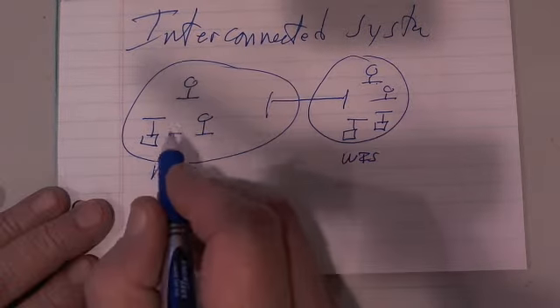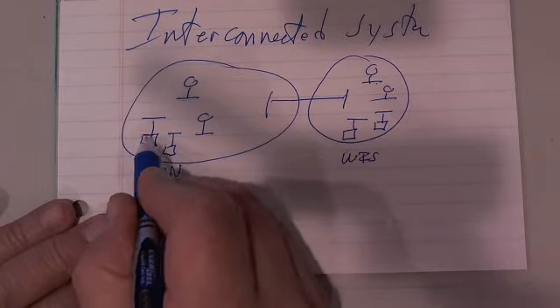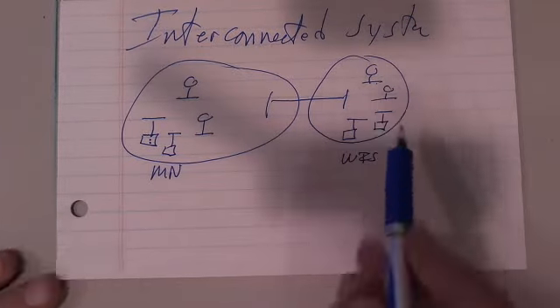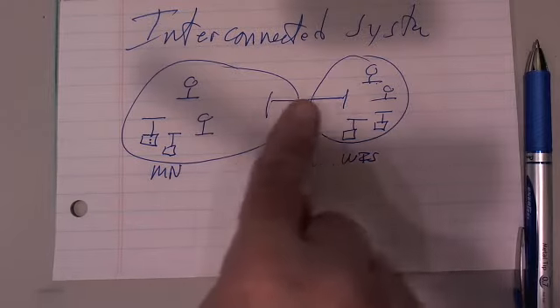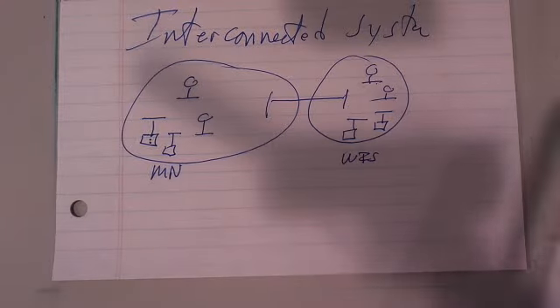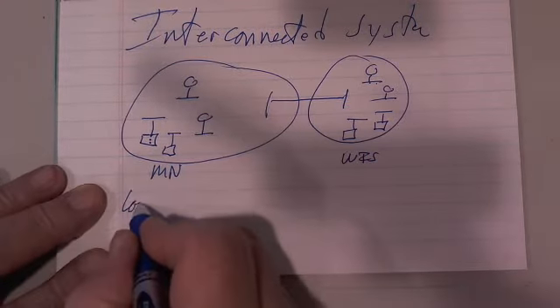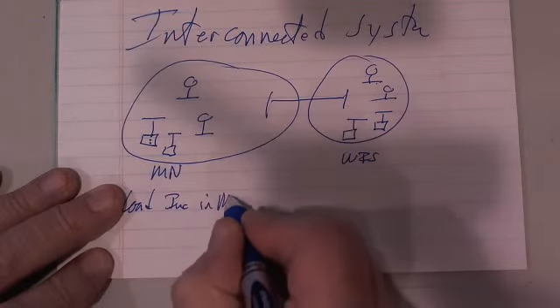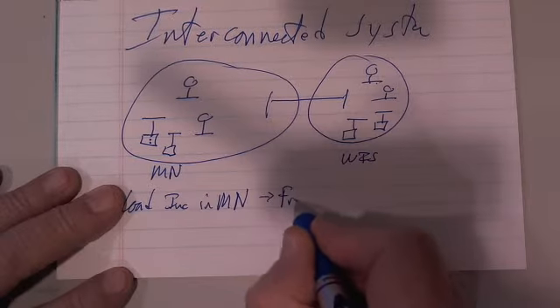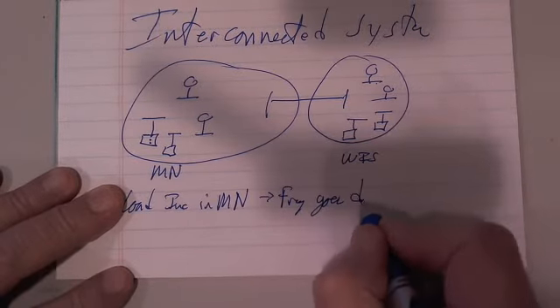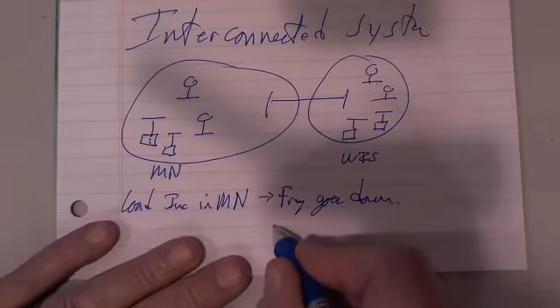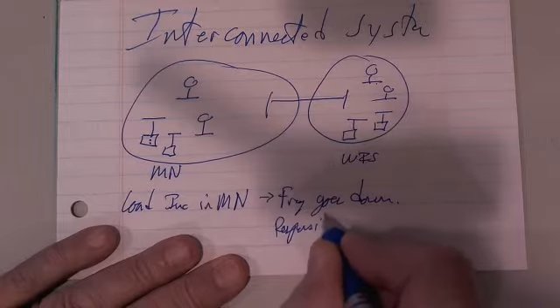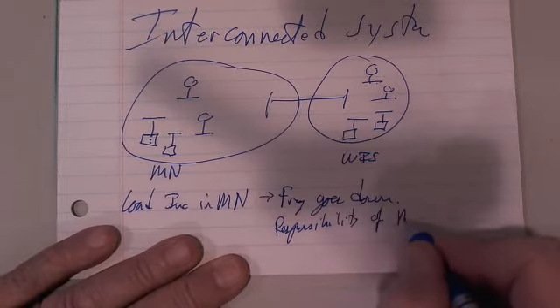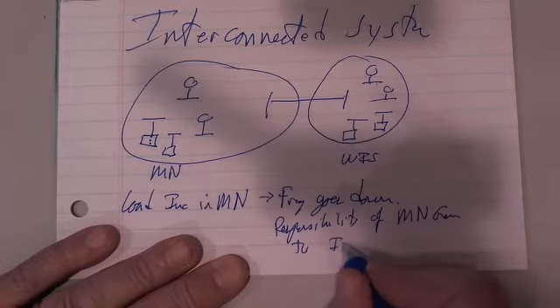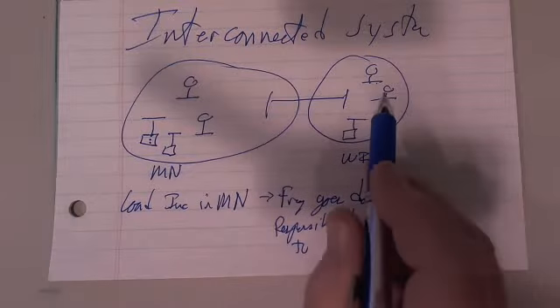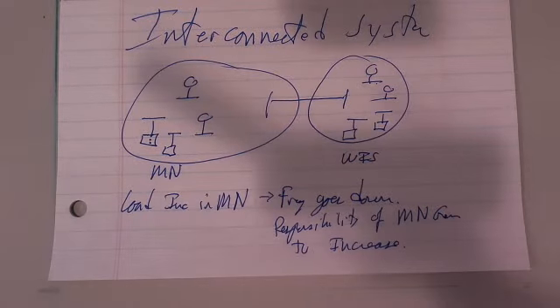The thing you want to notice is that if I have a sudden load increase in a load over here, or I lose a generator over here, the frequency is the same everywhere. But if I have a load increase in Minnesota, the frequency goes where? Down. Frequency goes down, and it's the responsibility of Minnesota generation to increase, not the generators in Wisconsin.